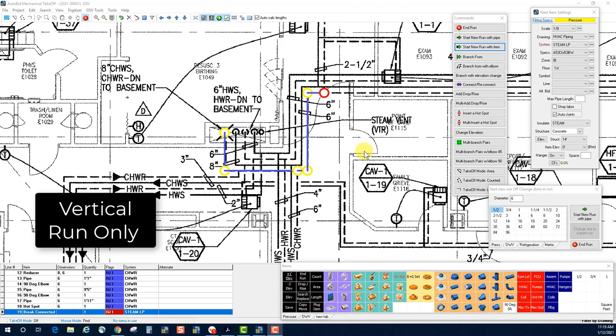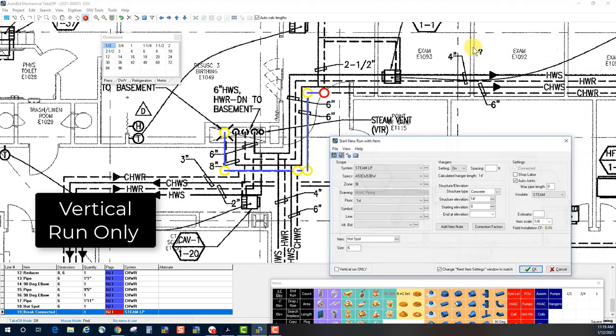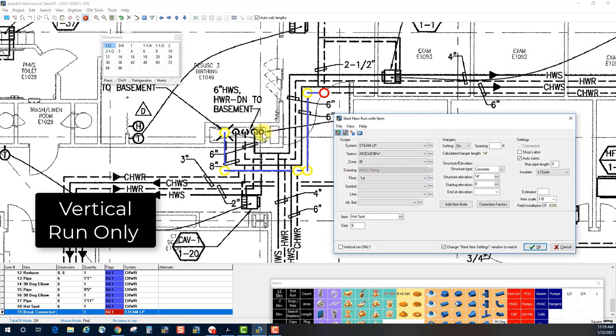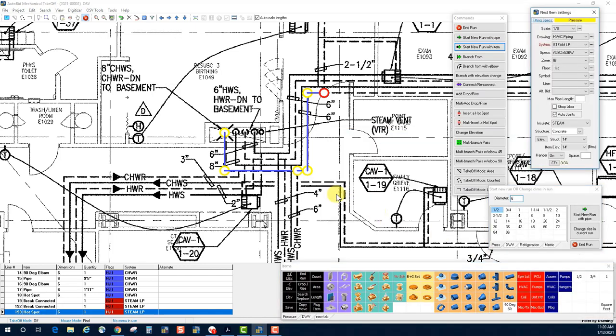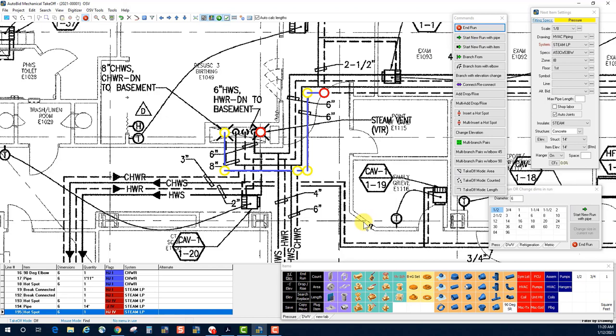Let's take a look at Start New Run with Item again, this time for a steam vent pipe that goes from floor to floor without going horizontal — it just passes through the floor. We can take advantage of the Vertical Run Only option in the lower left corner of the window. Verifying the system as steam low pressure, I'll start at elevation zero and go up to 14 feet to bring it up to the slab level for the next floor. When I click OK, the drag line is not attached because this was a vertical only.